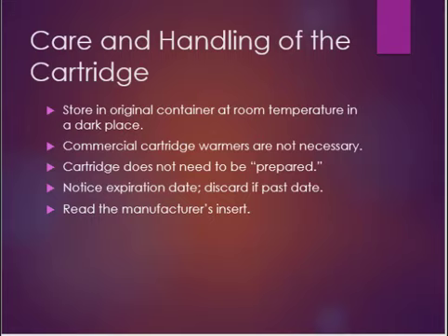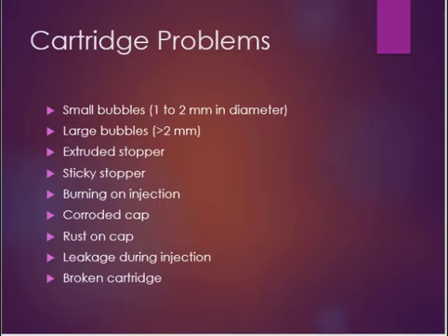So once again, they do not need to be warmed up before. The cartridges do come pre-sterilized, but some clinicians decide to wipe them down with the approved ADA disinfectant. You never want to place alcohol or sterilizing solutions onto that diaphragm, though, or onto the cartridges.